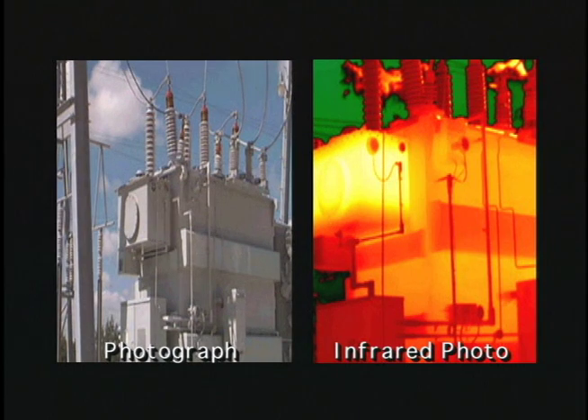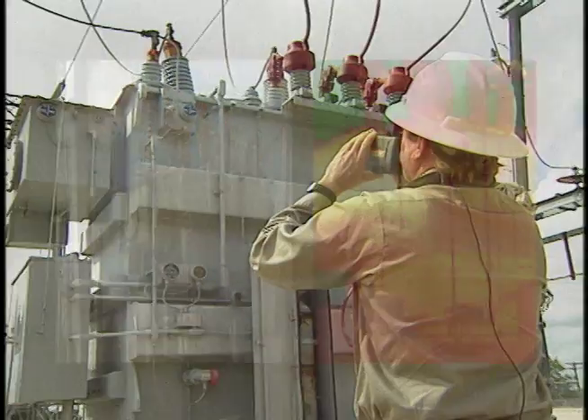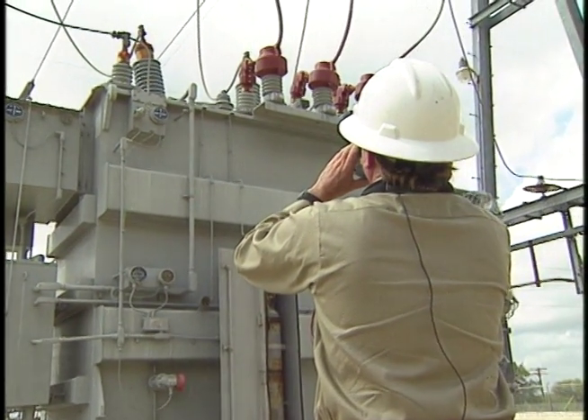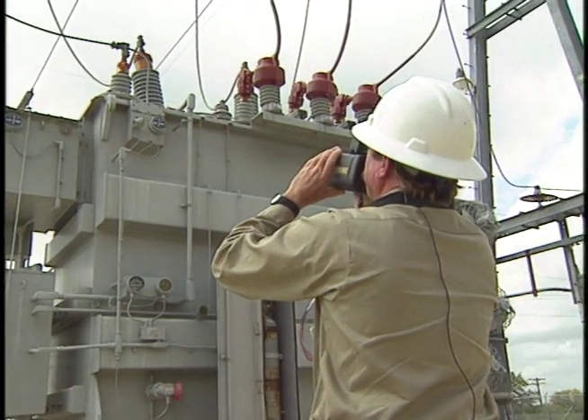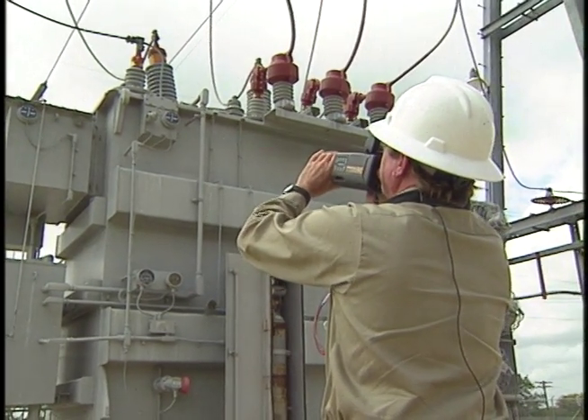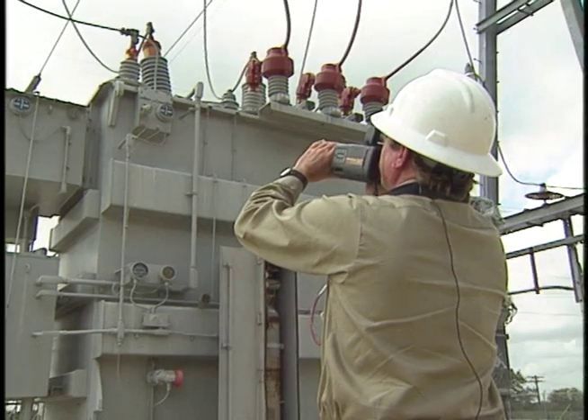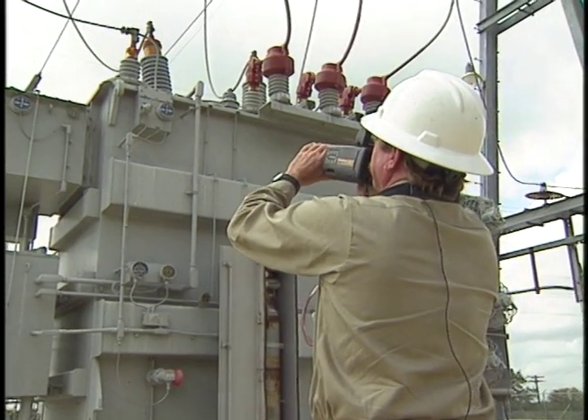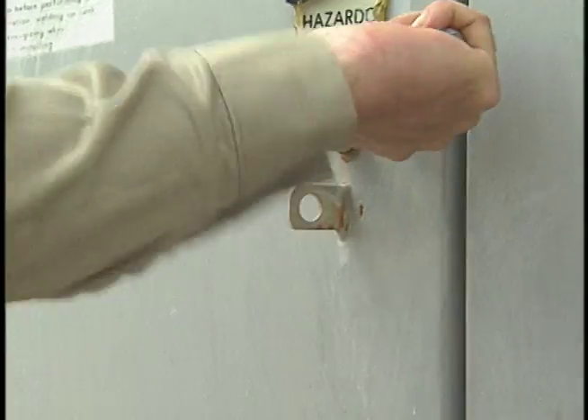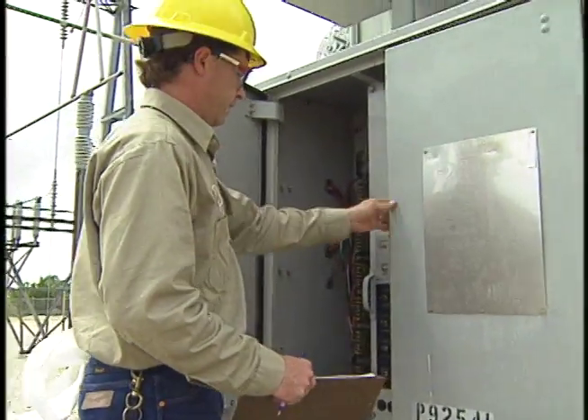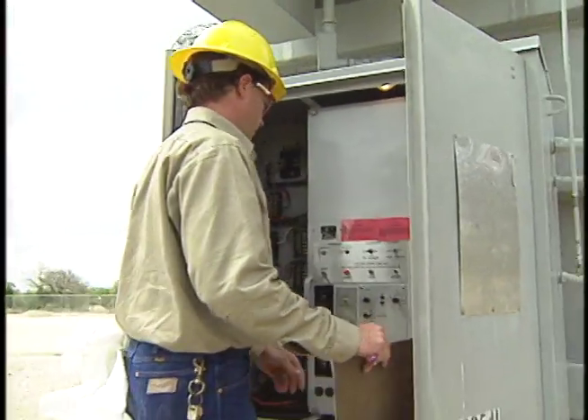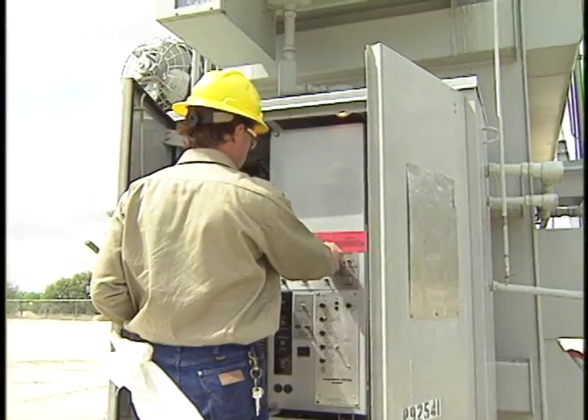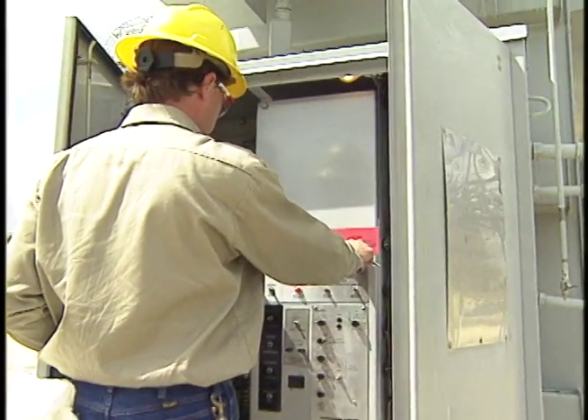The infrared camera sees a thermographic image of the transformer showing differences in temperature of the various components. We had a particular problem on this transformer a year ago. The reason I'm spending so much time looking at the LTC compartment is it was 11 degrees hotter than the main tank. The transformer was taken offline, and maintenance crews found loose connections inside that would certainly have caused much bigger problems in the near future.